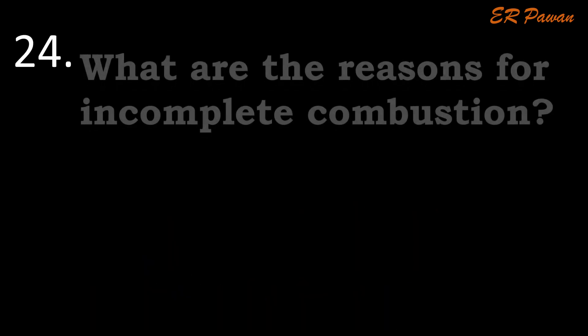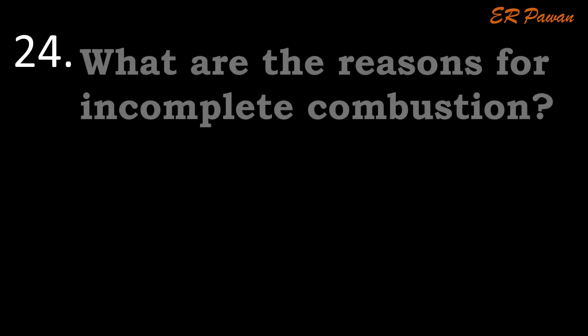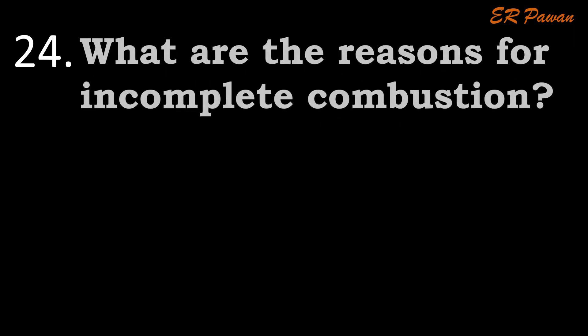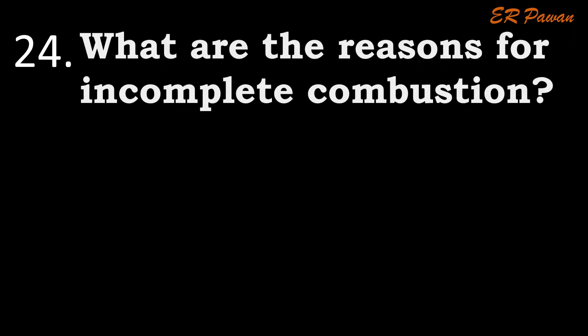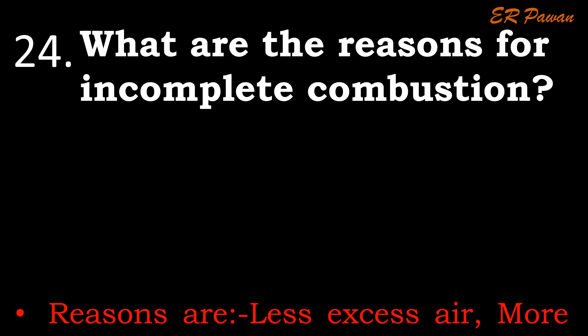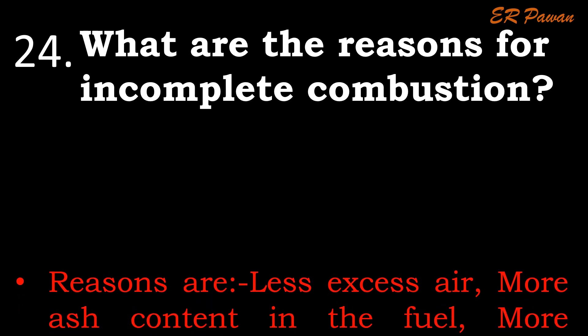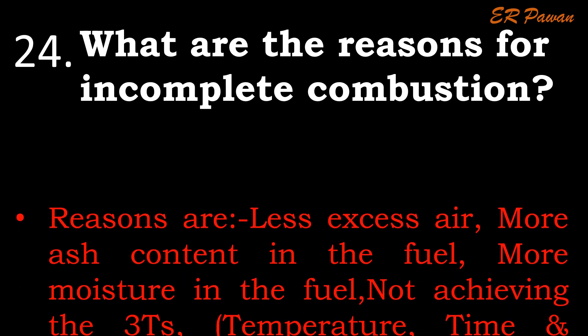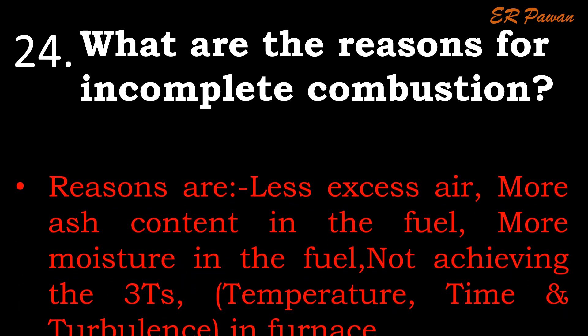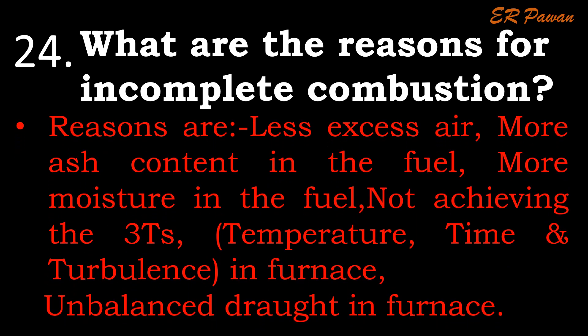Question 24: What are the reasons for incomplete combustion? The reasons are: less excess air, more ash content in the fuel, more moisture in the fuel, not achieving the three T's — temperature, time, and turbulence — in the furnace, and unbalanced draft in the furnace.